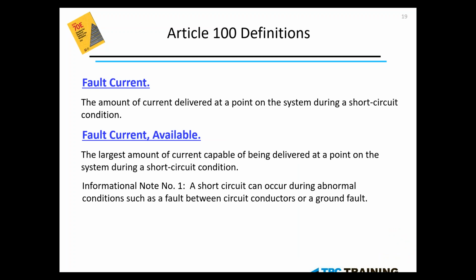The definition of fault current is any amount of current that is delivered on any point of the system during a short circuit condition. And the available fault current would be the largest amount or maximum amount of current capable of being delivered in that short circuit condition. How much is available in a system? Now, this is going to play a huge role in identifying the information on our arc flash labels, or warning labels. Now, those warning labels can either be done through the non-preferred method, which is called the PPE method, which we will cover later in our presentation next month with PPE, or the actual preferred method, which is the arc flash analysis method. So identifying the available fault current, the maximum amount of current that can be present during a short circuit.